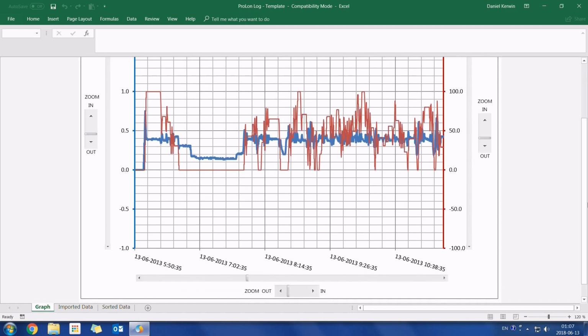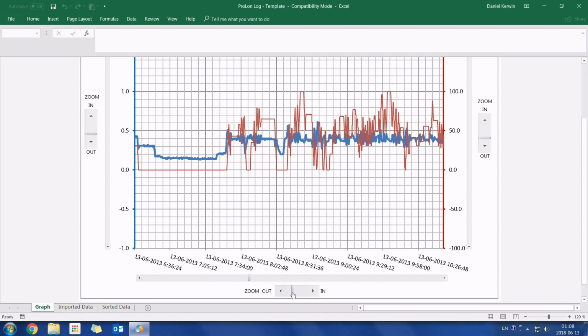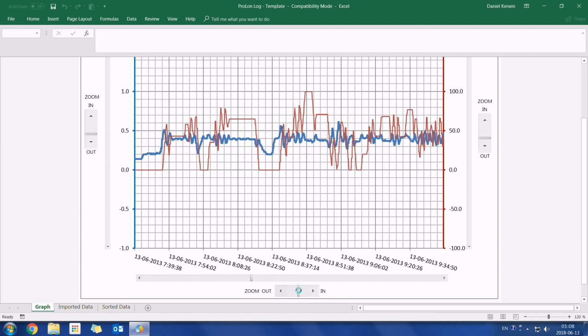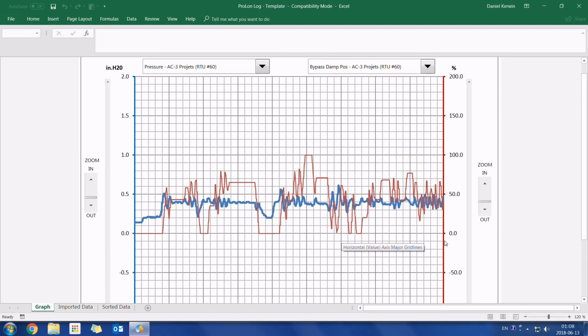If I want to zoom in a little bit, because our timestamp is pretty large, on the left hand side here it's 5:50 a.m. and this line here is almost 10:40 a.m., so this is almost our entire morning. If I just want to take a closer look at it, I can zoom in, and there we go. Now we can look at the duct static pressure versus the bypass damper position.